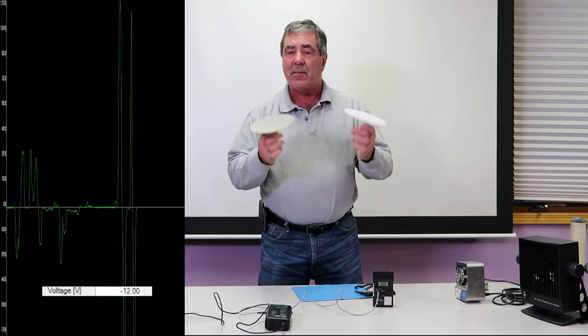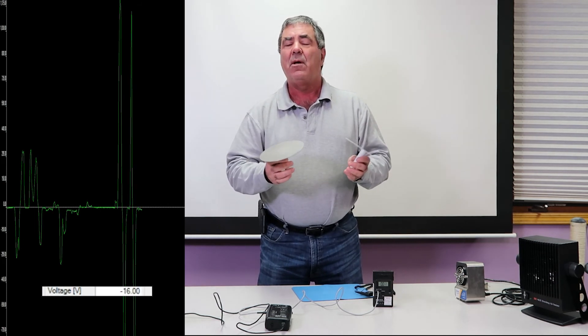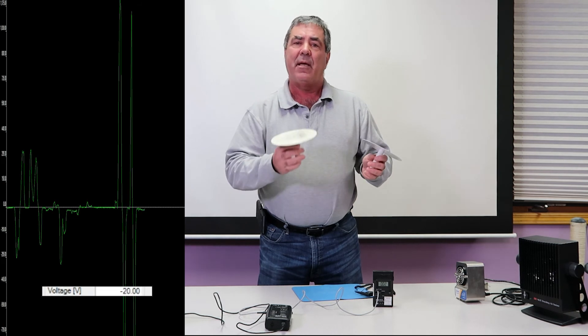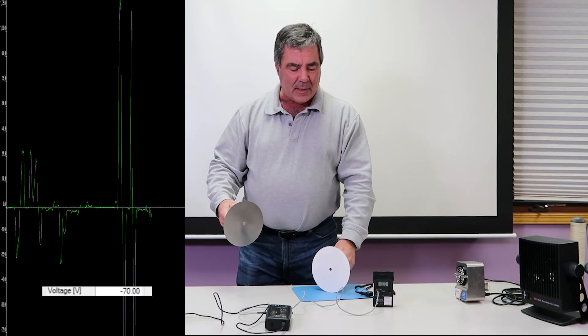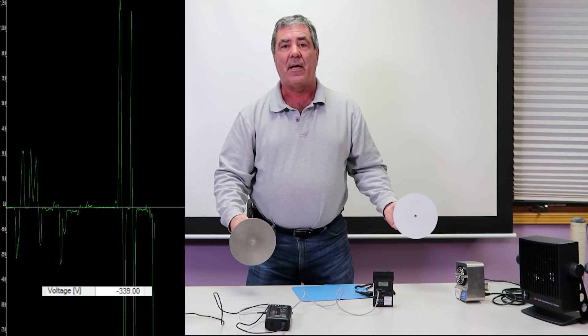So in processes, contact and separation of two materials always results in charging. You can get rid of them easily by grounding your metal. In the case of an insulator, if you can't, you need to use ionization.